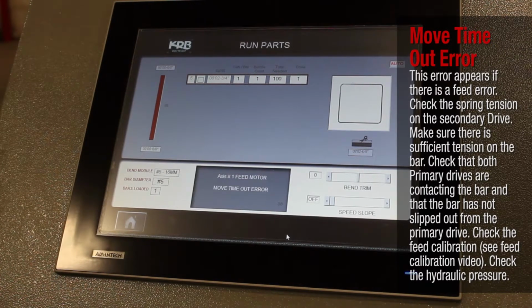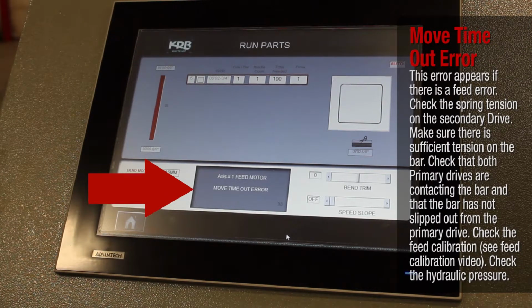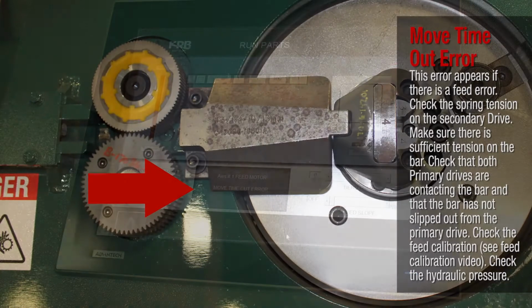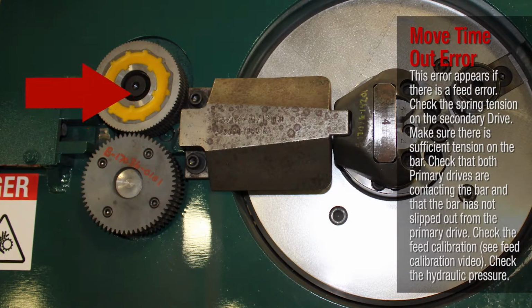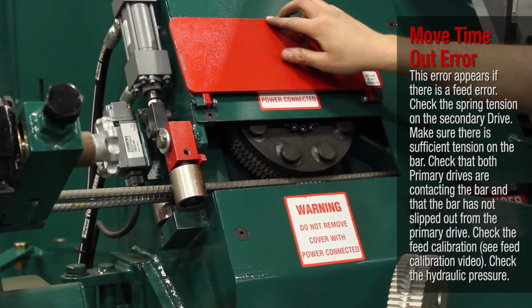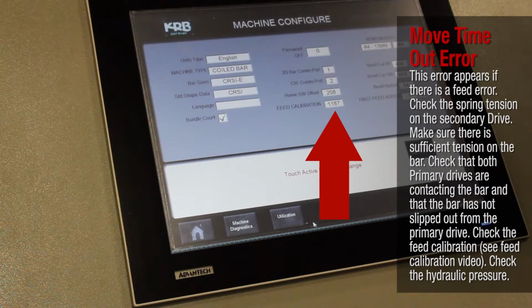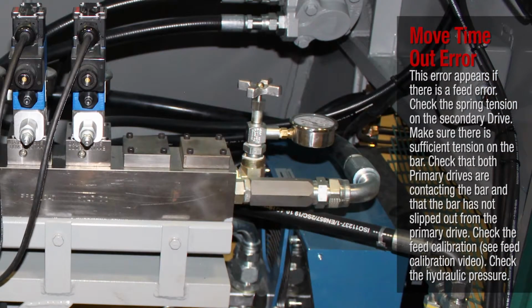Move timeout error. This error appears if there is a feed error. Check the spring tension on the secondary drive. Make sure there is sufficient tension on the bar. Check that both primary drives are contacting the bar and that the bar has not slipped out from the primary drive. Check the feed calibration. See feed calibration video. Check the hydraulic pressure.